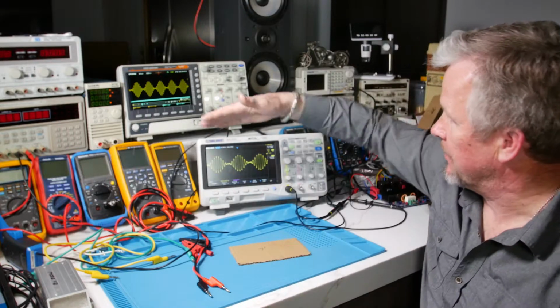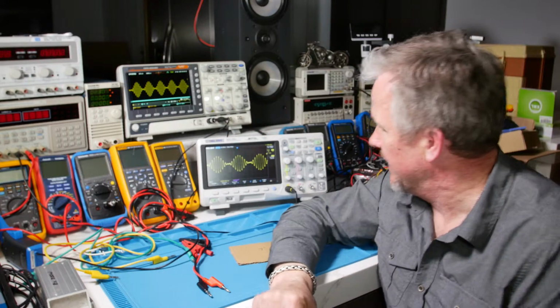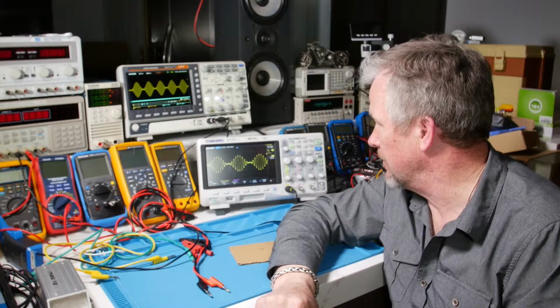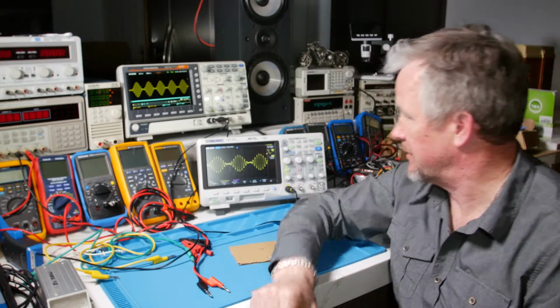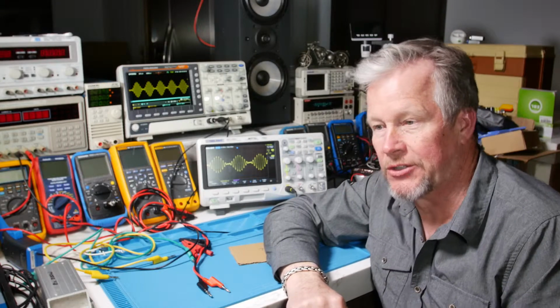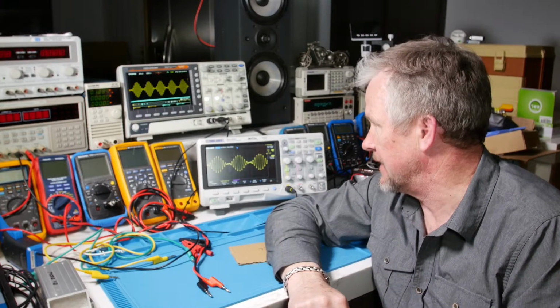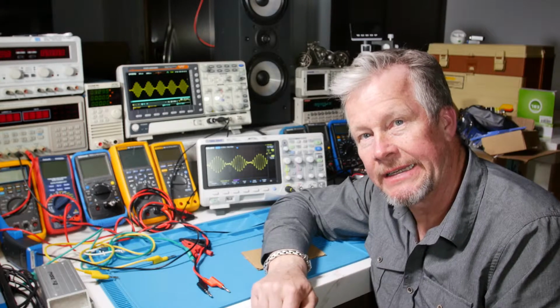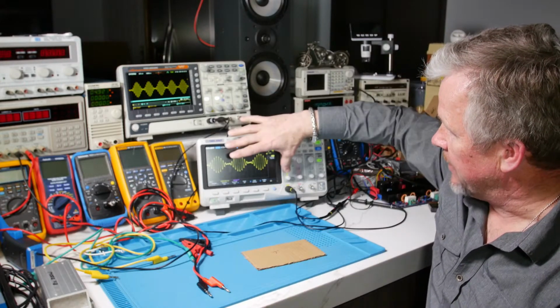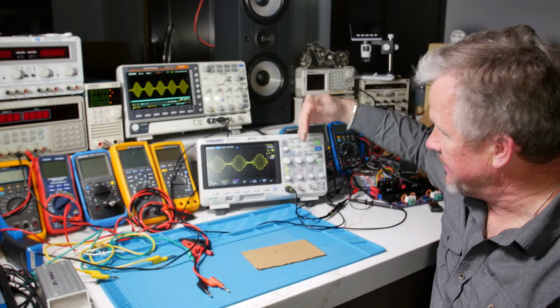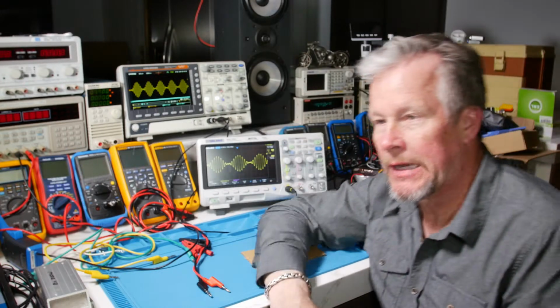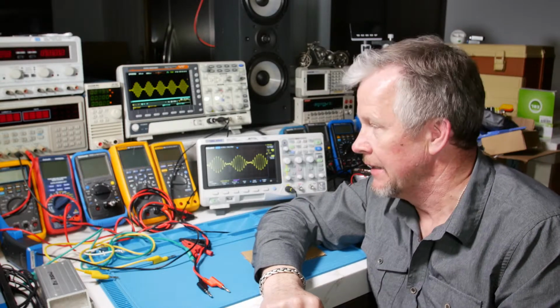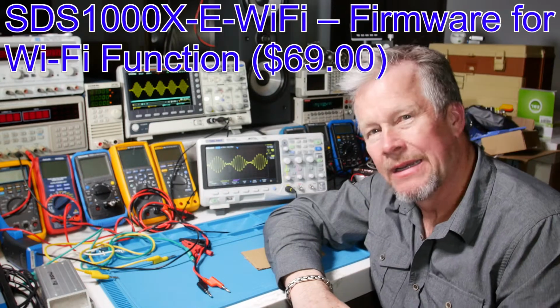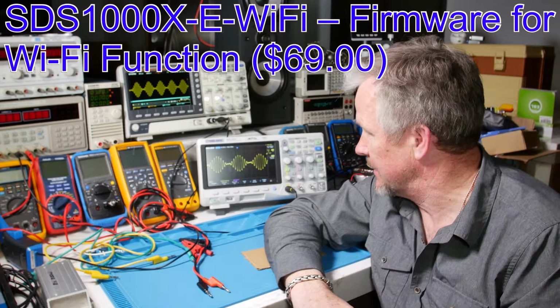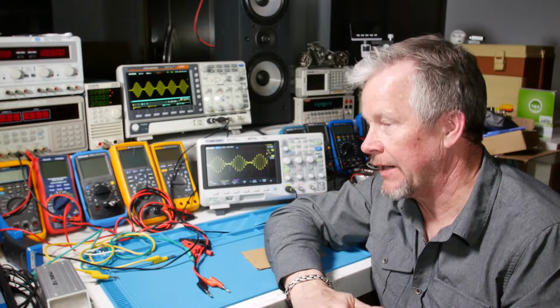I'm going to show a picture of the 1202 XE so you can see how they look very similar. The 2-channel versions look very similar, especially on the non-digital option of the XE. It looks very similar to this scope. So the XE, other than the screen being a little smaller, it has deeper memory on the FFT, but it also has some web control options. And it also has a Wi-Fi option that you can plug in the USB. I don't think that works for this one. It does for the XE, so you can get a Wi-Fi upgrade.